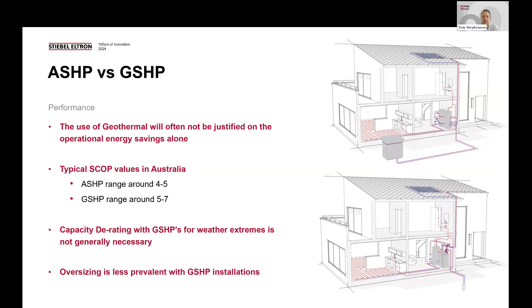So the big thing I suppose we need to mention when we talk about the comparison between air source and ground source is that we don't generally need to factor in derating of the systems. So if we've got a 100 kilowatt load, we're designing a heat pump solution for 100 kilowatts and not necessarily providing 150 kilowatts worth of heat pumps because of circumstances throughout the year and peak climate conditions that would see those not be able to reach the peak demands. So oversizing is less prevalent with ground source heat pumps, which is important from a costing perspective because it decreases then the ground heat exchanger or the water body exchanger, whatever it may be, to equalise that cost benefit argument.